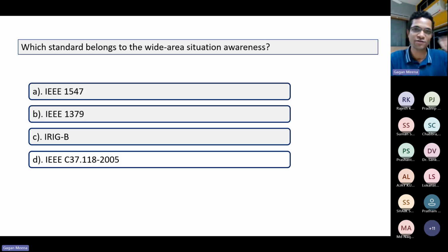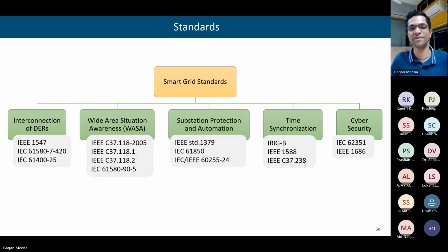Which standard belongs to wide area situation awareness? WASA. 1547 is for interconnection of DER. This one is for time synchronization. This one is for PMU. These are different standards, some important ones you should always try to remember: 1547, 61400, and for WASA this PMU measurement synchrophasors is C37.118, and 61850 for substation automation, and this one for time synchronization.